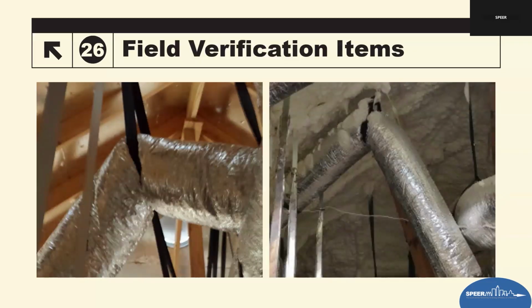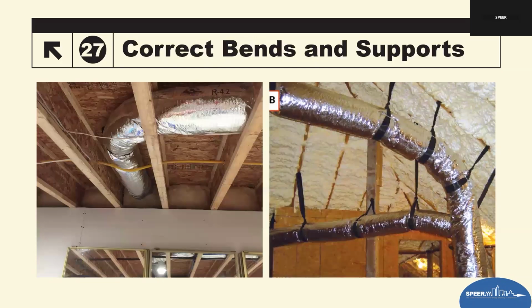Same thing with this. The one on the left should actually have the minimum of 2 straps. I know it's a strap every 4 feet, but if you've got a 90-degree bend, let's put a strap on at least before and after that 90 and hold that to a sweeping turn, not a sharp bend like what we see in the one on the right, which is just a very sharp bend. Push it all the way to the attic itself and then drop it all the way down. That strap could have been much, much longer and allow for that bend to be less. Kind of like this. This is the best way to do it.